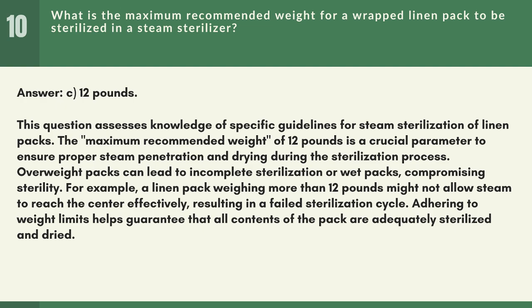The maximum recommended weight of 12 pounds is a crucial parameter to ensure proper steam penetration and drying during the sterilization process. Overweight packs can lead to incomplete sterilization or wet packs, compromising sterility. For example, a linen pack weighing more than 12 pounds might not allow steam to reach the center effectively, resulting in a failed sterilization cycle. Adhering to weight limits helps guarantee that all contents of the pack are adequately sterilized and dried.